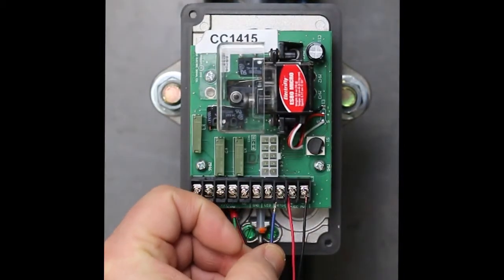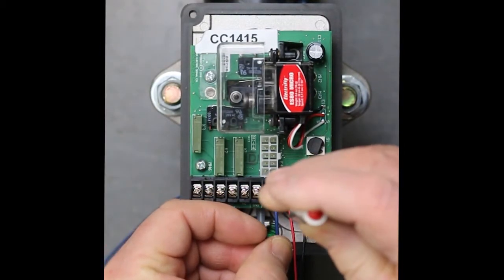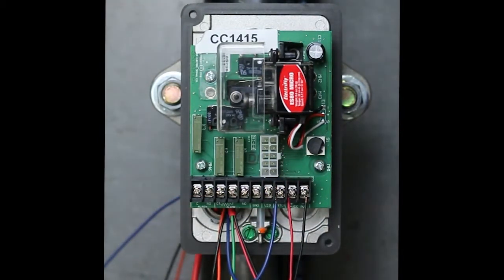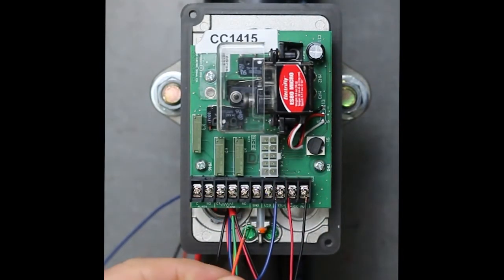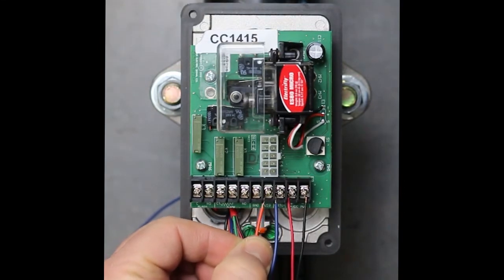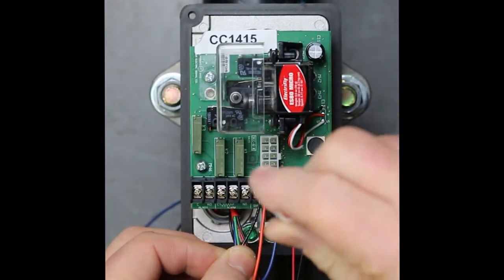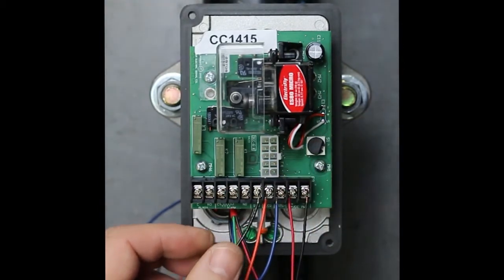The next terminals are for the ATC test switch. The blue wire from the ATC goes to the terminal marked switch. The orange wire from the ATC goes to the terminal marked LED to light the status LED in the ATC test switch. The black wire from the ATC goes to the terminal marked ground.